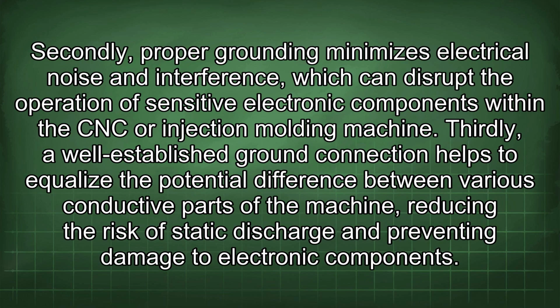Secondly, proper grounding minimizes electrical noise and interference, which can disrupt the operation of sensitive electronic components within the CNC or injection molding machine. Thirdly, a well-established ground connection helps to equalize the potential difference between various conductive parts of the machine, reducing the risk of static discharge and preventing damage to electronic components.